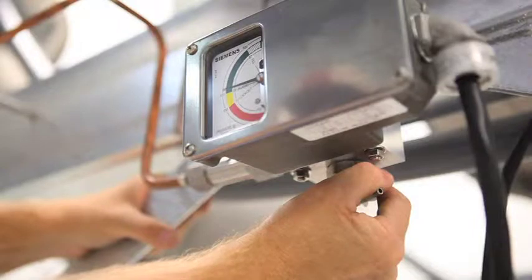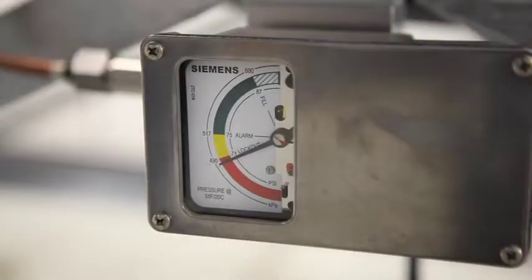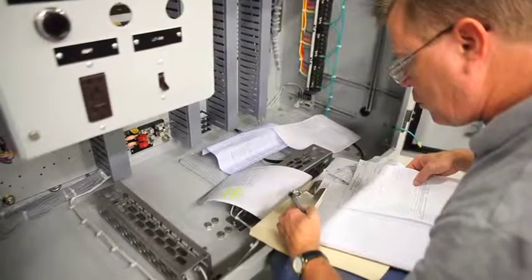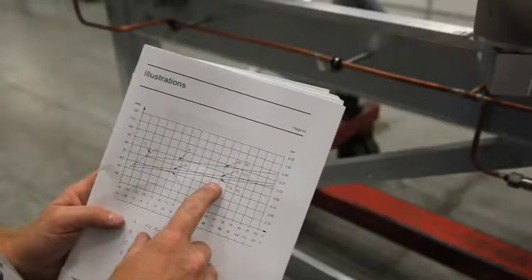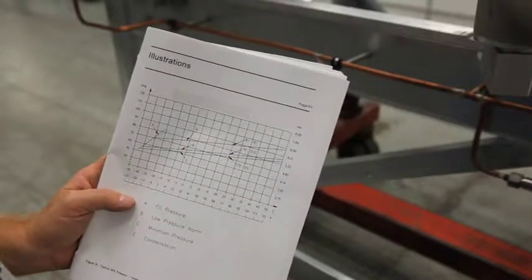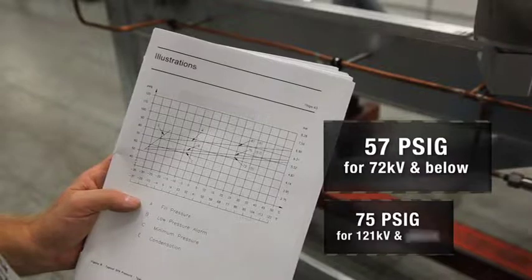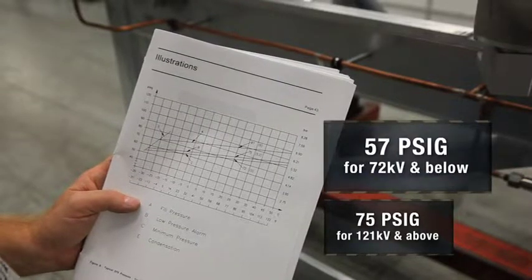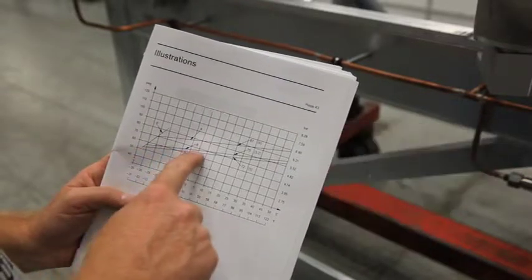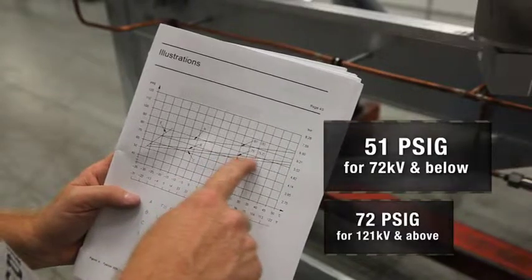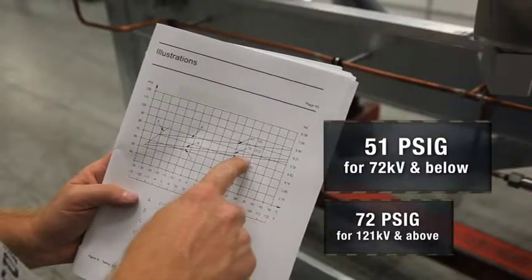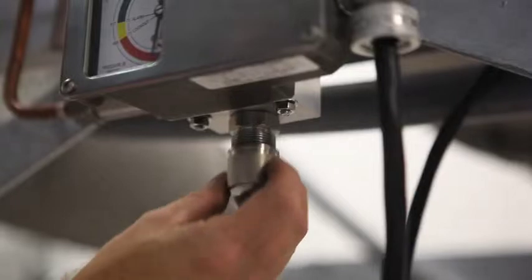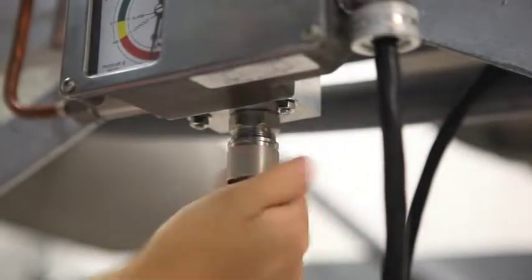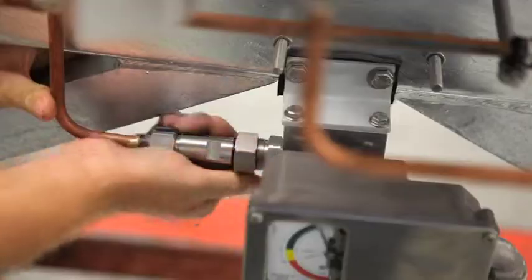Drop the SF6 pressure using the bleed valve. Record the alarm and cutout pressures with the ambient temperature and refer to the chart. The pressure should be the equivalent of 57 to 75 psig at 68 degrees for the alarm contact and 51 to 72 psig at 68 degrees for the cutout contact. When pressure readings are completed, open the shutoff valve and replace any SF6 gas lost in the testing process.